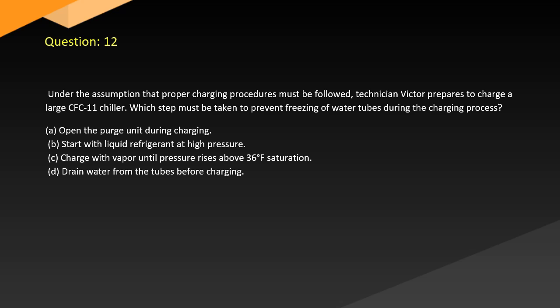Question 12. Under the assumption that proper charging procedures must be followed, Technician Victor prepares to charge a low-pressure CFC-11 chiller. Which step must be taken to prevent freezing of water tubes during the charging process? A. Open the purge unit during charging. B. Start with liquid refrigerant at high pressure. C. Charge with vapor until pressure rises above 36 degrees saturation. D. Drain water from the tubes before charging.